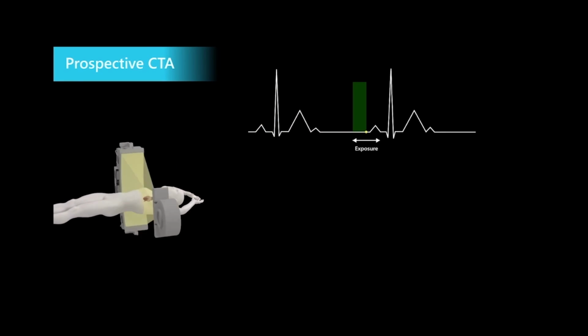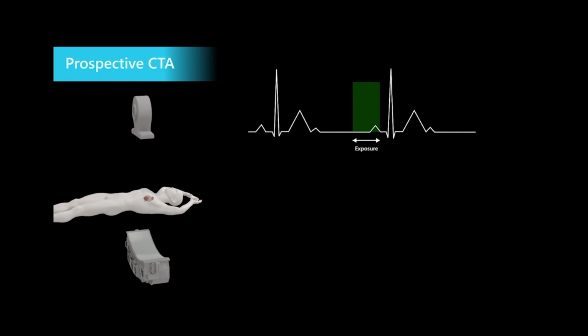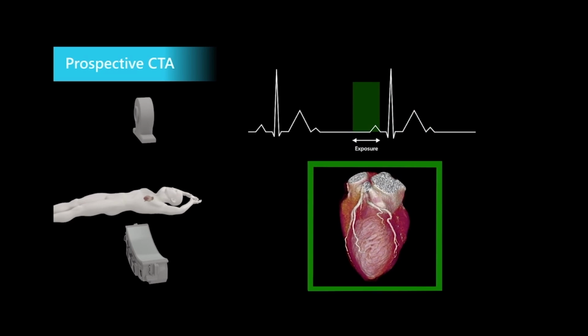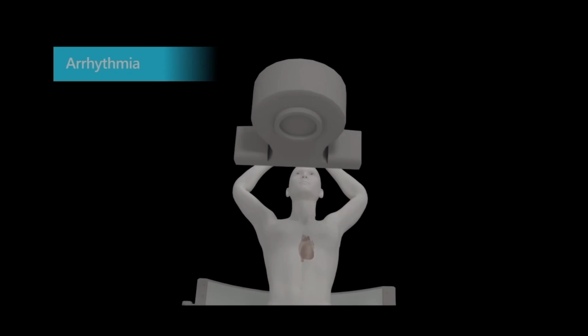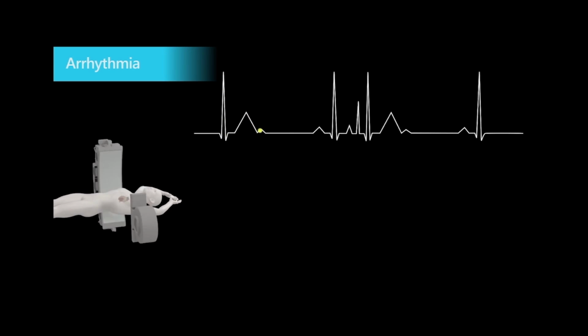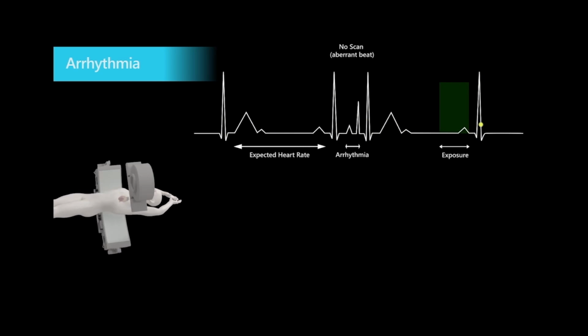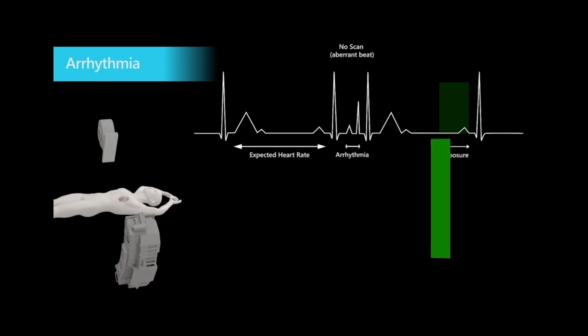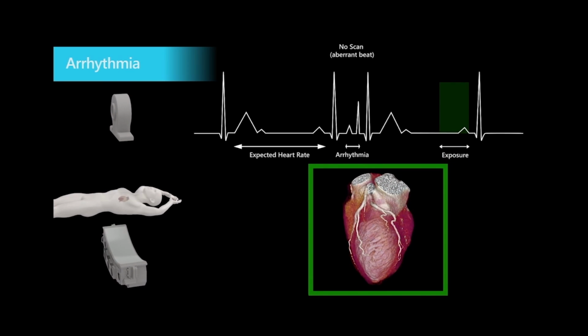To evaluate the coronaries, the acquisition needs to occur during the heart's quiescent period. Canon's Sure Cardio Suite, which includes advanced phase prediction, ensures scanning at the right phase. Arrhythmia detection and handling prevents mistimed scans. When an arrhythmia or irregular heartbeat occurs, the advanced algorithm detects the aberrant beat and adjusts to ensure a successful scan. This may mean delaying the acquisition until a stable heartbeat occurs, or switching to continuous mode in the case of a gated helical scan.